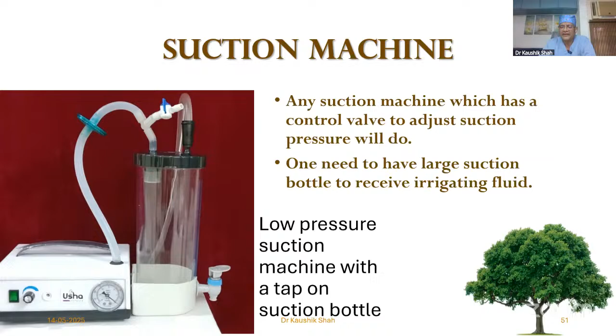If you do not want to use a suction, you detach the suction tube. Keep the suction machine on throughout the procedure. When the suction is working, only air will be sucked from the reservoir. If you close the suction control opening, then the pressure is transmitted inside. Some amount of suction is transmitted because it is sucking both from the suction control opening and inside.